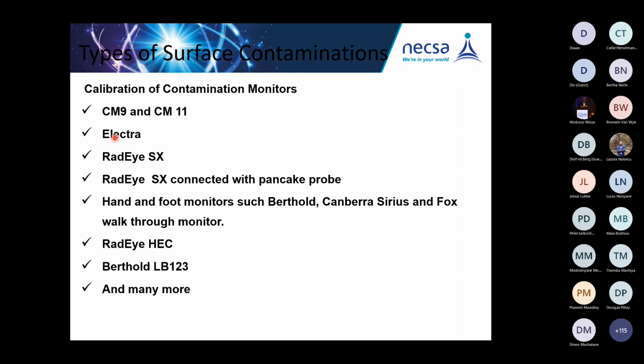The Electra GM is a 2-in-1 instrument. It can measure radiation survey, and it can also measure surface contamination. Then we've got the SX, which is the replacement of the Electra 1A. The SX connected with the pancake probe is the one which replaced the Electra GM, because this instrument comes with one pancake probe, a Geiger-Müller tube, and also a radiation survey probe. The instrument is calibrated with 2 probes simultaneously. We start with the contamination and then with the radiation.